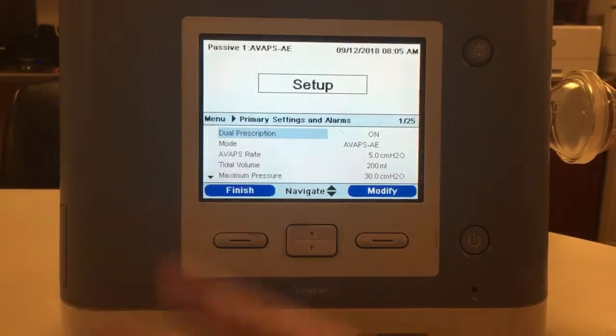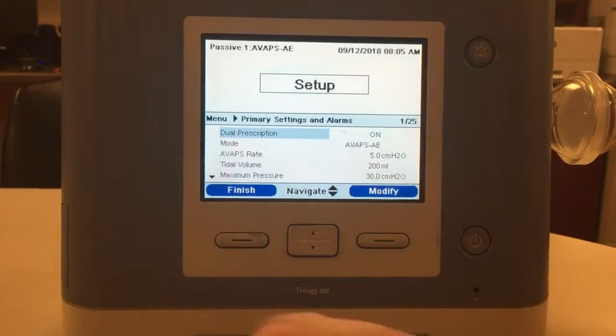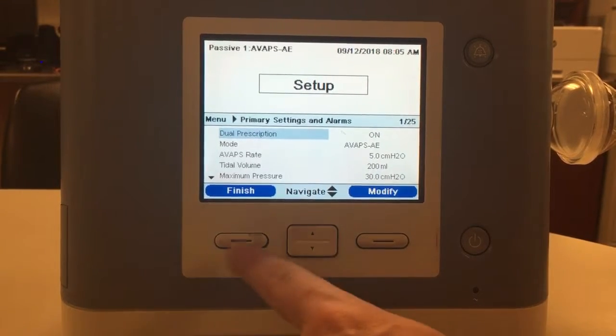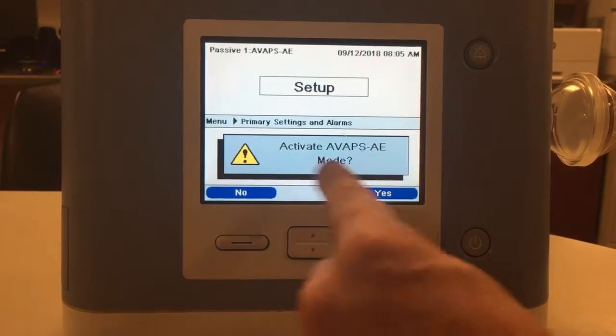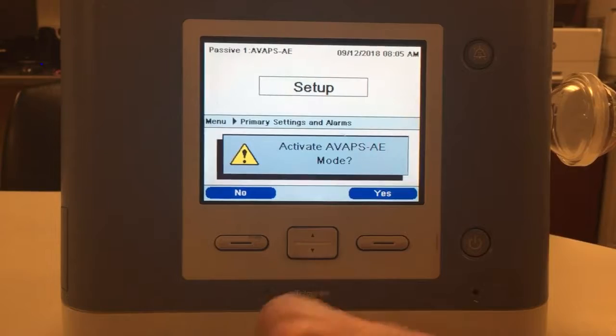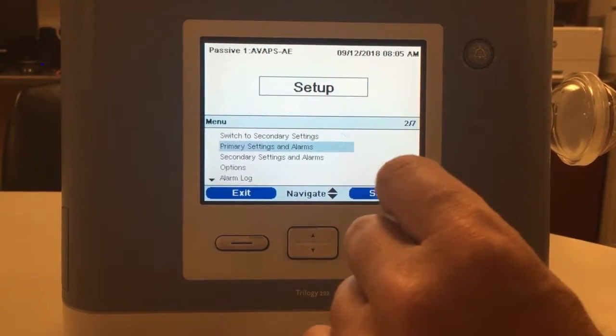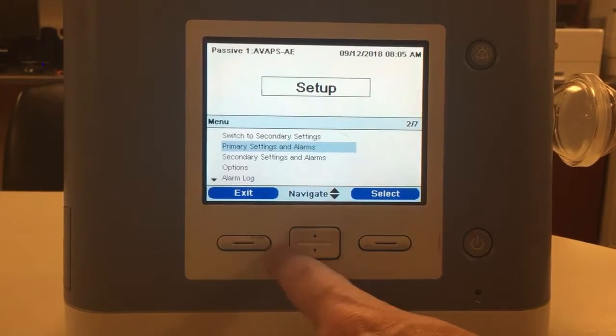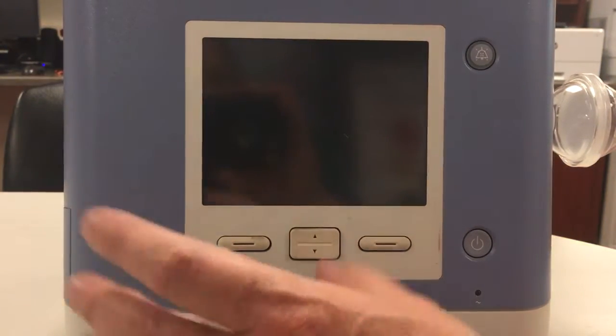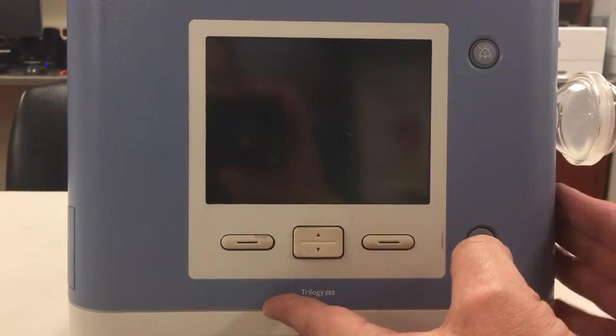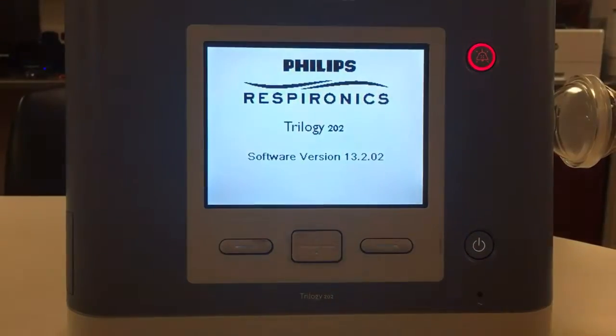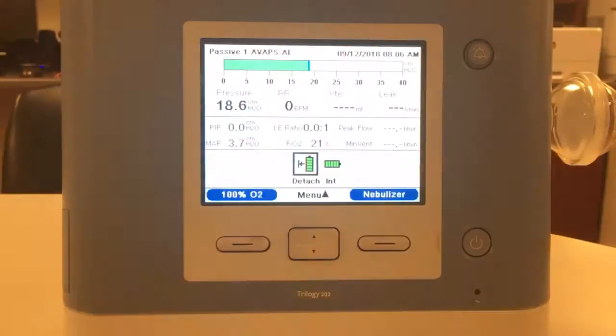Of course, to finish off, you always want to make sure that you follow all the way through the prompts. So you hit finish, and activate AVAPS AE mode will come up, and you always hit yes. So never walk away unless you've hit all the buttons, including exit. Now, because we entered the provider menu with the ventilator off, it is going to go off. But once we turn it on, we'll go back on AVAPS AE mode.